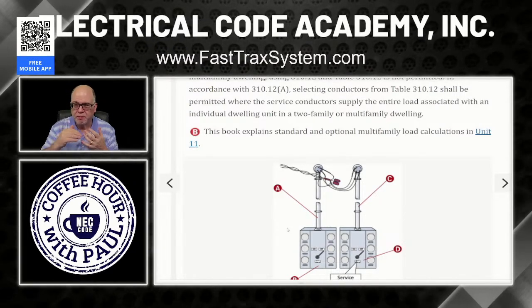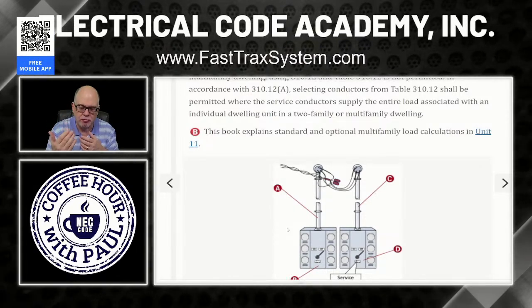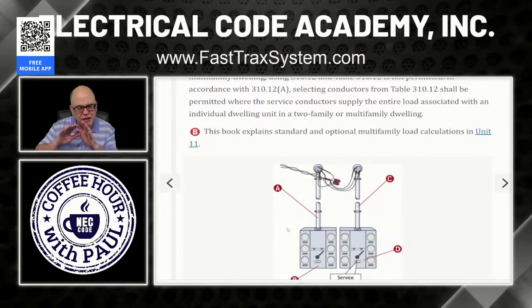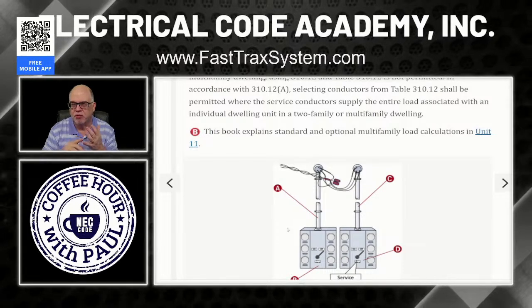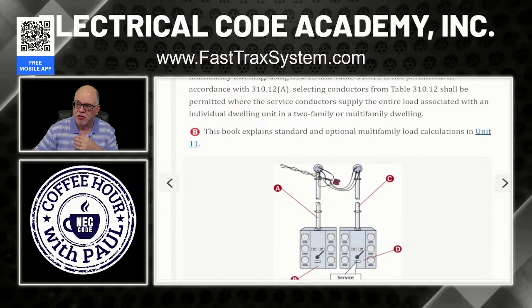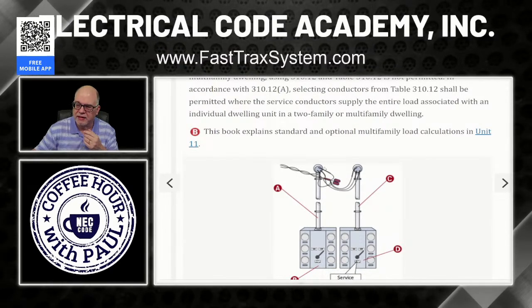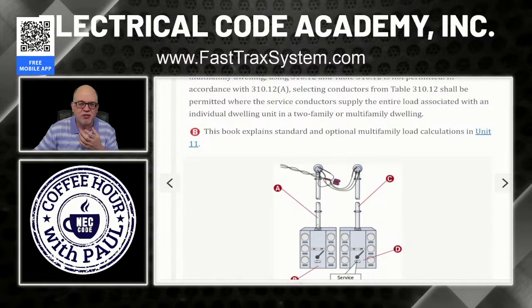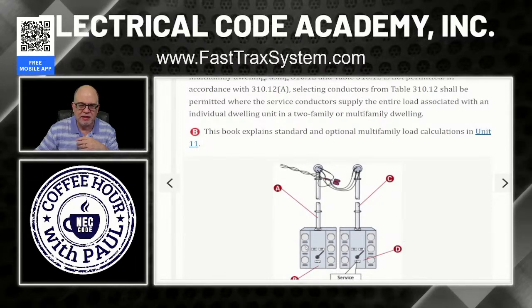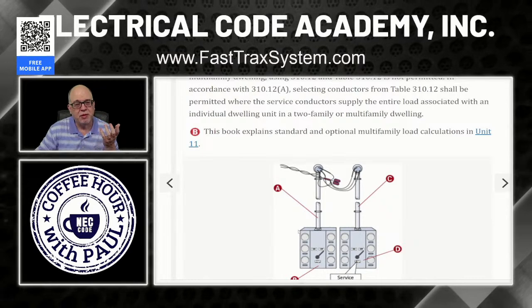I know that's going to be confusing for some people. Pause and go ahead and look up the 83% rule in 310.12. I'm not going to explain it here because we're going to save that for a different video. I just want you to know that it's not going to apply here. Why? Because these service conductors right here, coming from the service drop, are not seeing the entire load of the entire building. They're only seeing the load associated with these six units. Right? So therefore, 310.12 can't be applicable here.